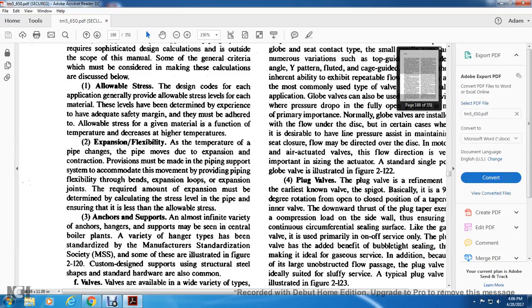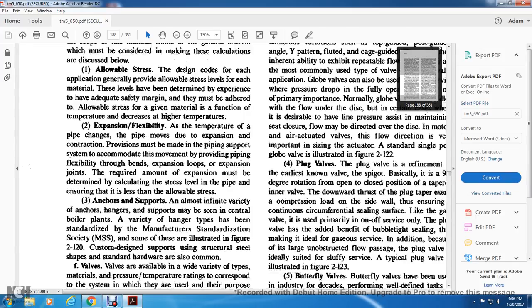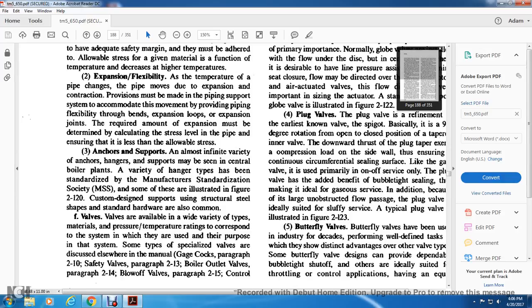Expansion and flexibility. As the temperature of the pipe changes, the pipe must move due to expansion and contraction. Provisions must be made in the pipe supporting system to accommodate the movement, providing pipe flexibility with bends, expansion loops, or expansion joints. The amount of expansion must be determined, calculating stress in the pipe and ensuring the lines have less than the allowable stress.